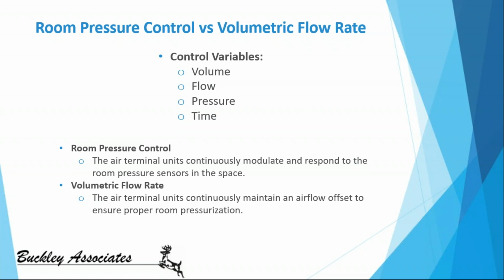On the other hand, if we chose to utilize control via volumetric flow rate, we only need to pay attention to how much air is going into the space and how much air is leaving the space. There's no longer a time variable. So no matter what is going on in the room, whether doors are open or closed, we're constantly assured that the pressure, so our air changes in that space, are going to be correct.